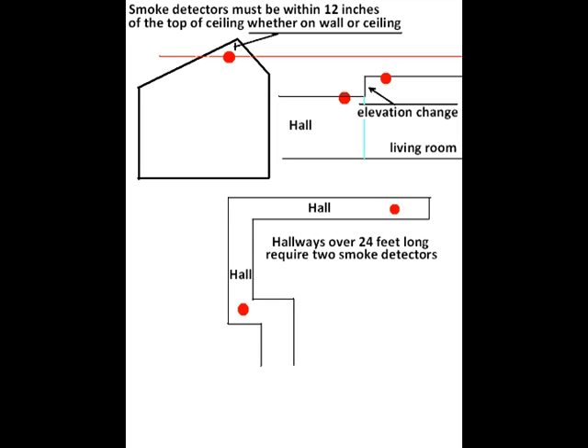The bottom diagram shows a very long hallway. If it exceeds 24 feet in length, it requires two smoke detectors. Ideally, you want those to be about 15 feet apart, maybe a little bit more.